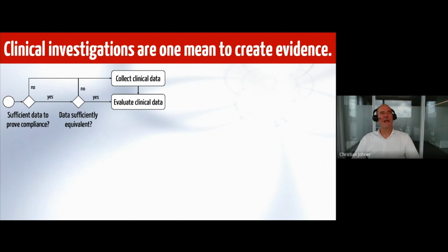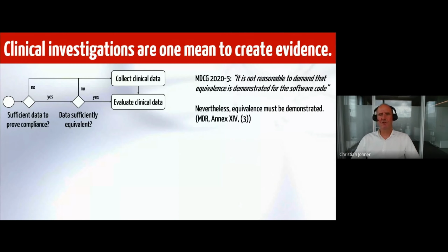Now the question is, when are data sufficiently equivalent? Sometimes I hear the notion that the algorithm must be exactly the same. And this is not quite true. We have an MDCG document with a short sentence saying that it is not even reasonable to demand that. But they do not describe what is enough in that particular case. And the MDR says the equivalence, also the technical equivalence, must be demonstrated, and this explicitly includes the algorithms.